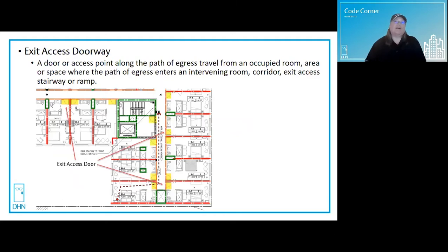Just a couple more definitions. An exit access doorway is a door or access point along the path of egress travel from an occupied room, area or space where the path of egress enters an intervening room, a corridor, an exit access stairway, or ramp. All of the doors that are highlighted are exit access doorways.